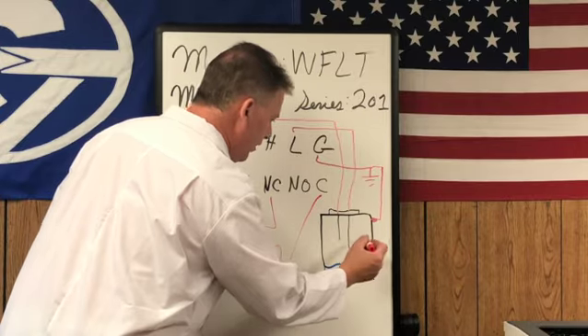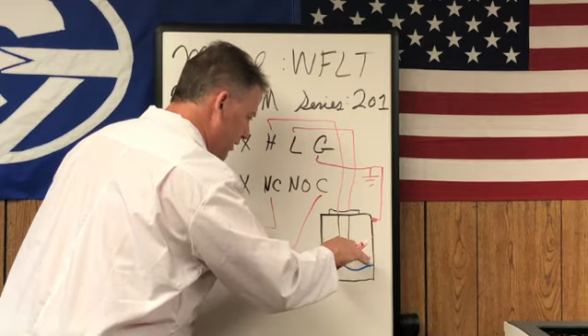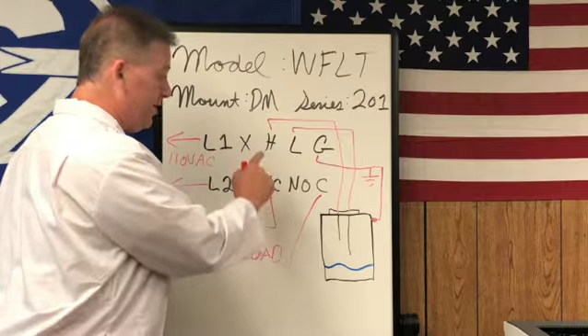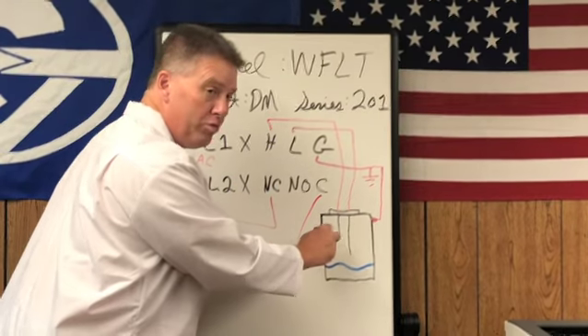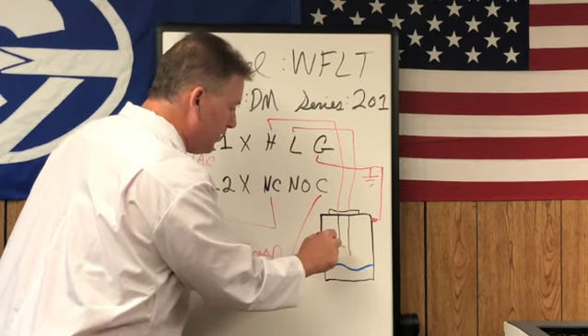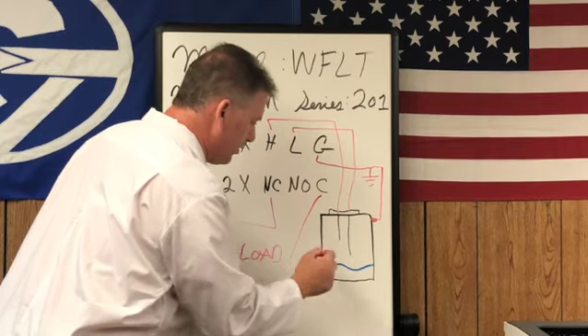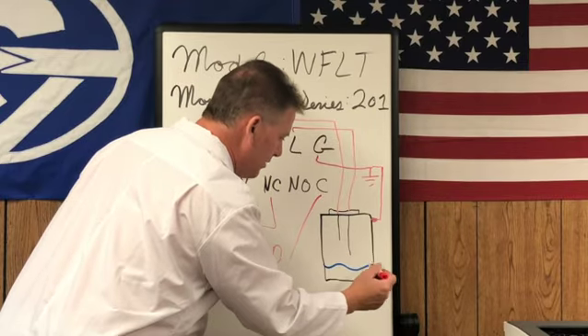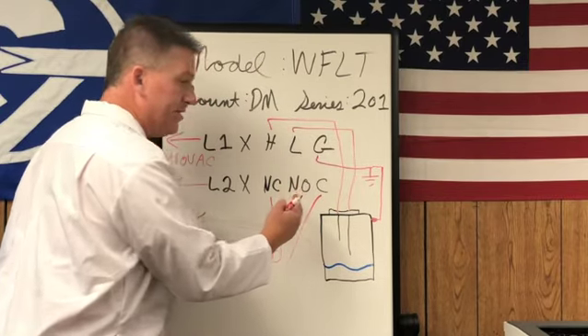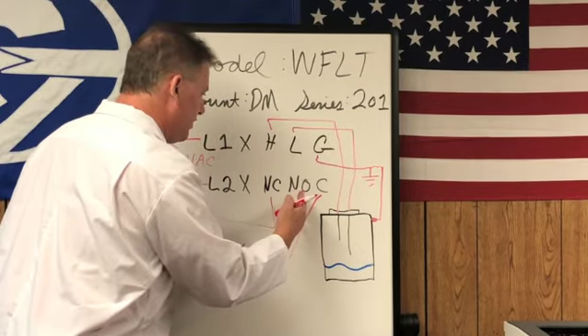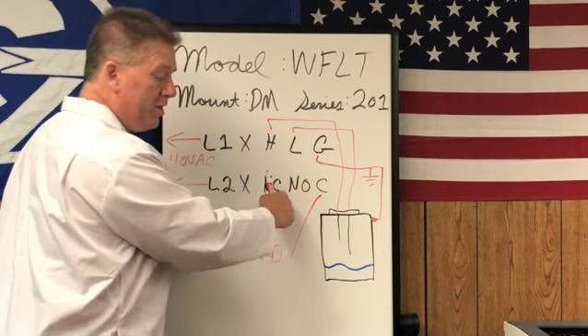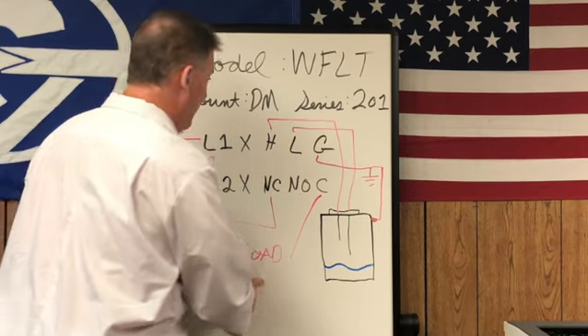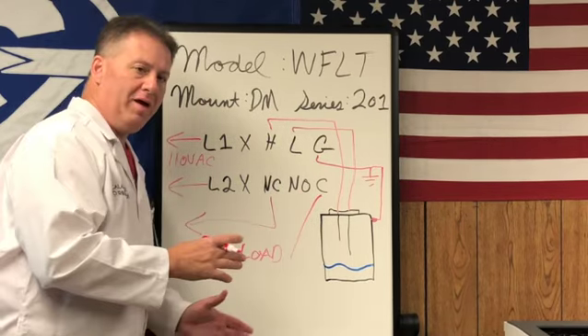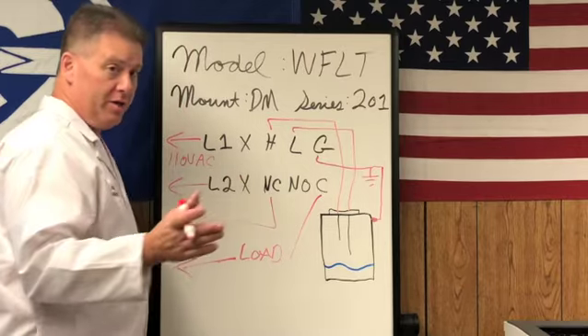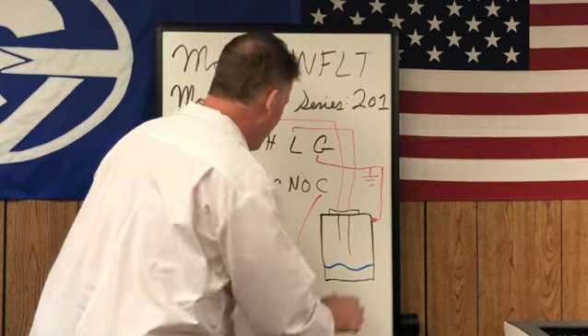When that happens, the liquid is going to drop below the high level probe. The relay is going to stay energized because your low probe is acting as a holding circuit for the level control. The second the liquid drops below the low probe, it's going to say, oh, no connection. The relay is going to de-energize. Normally closed will be closed again, and it will turn your load on. So back to what I was talking about before, single point on-off switch. That is not a problem.